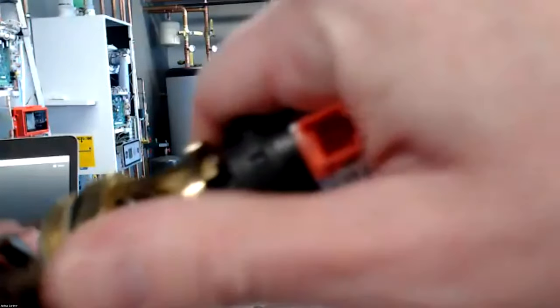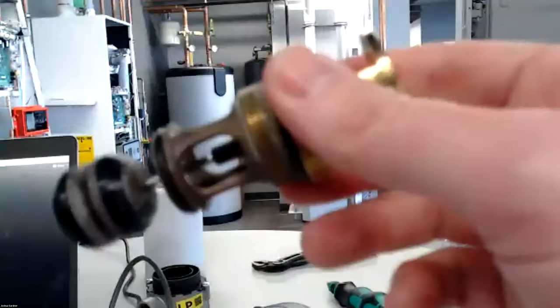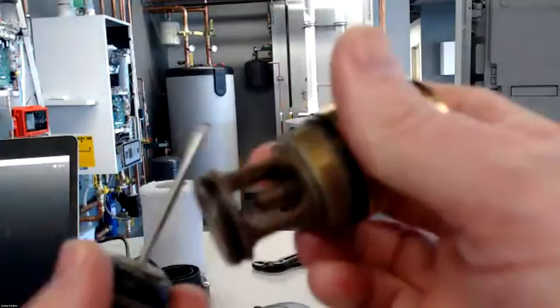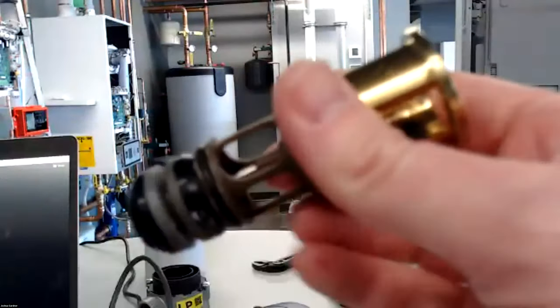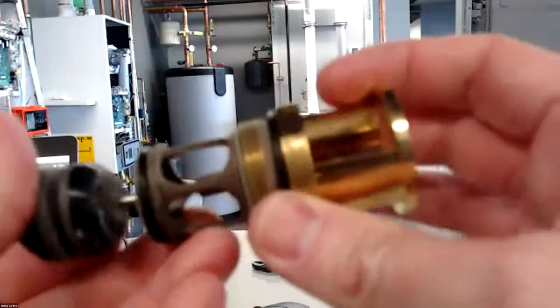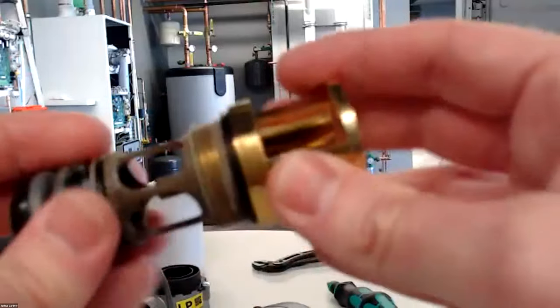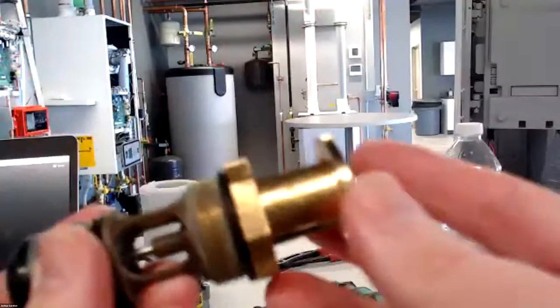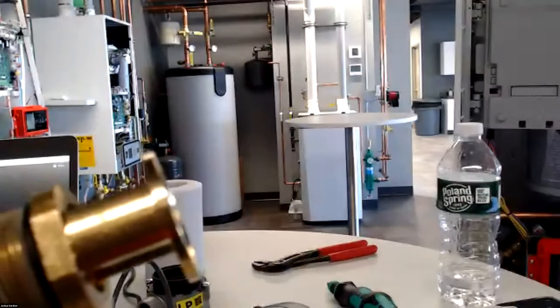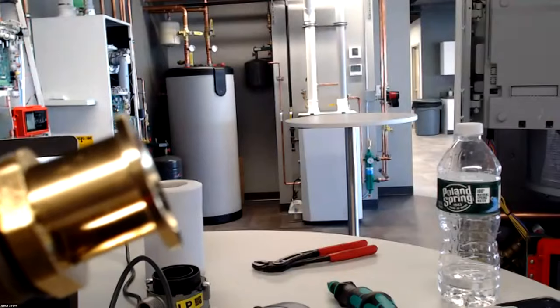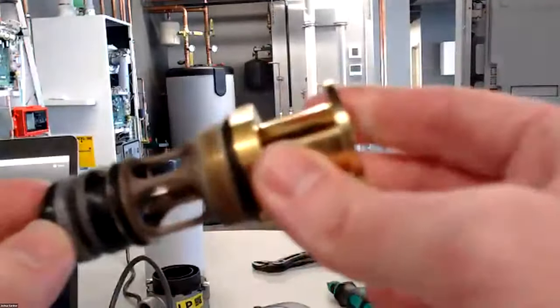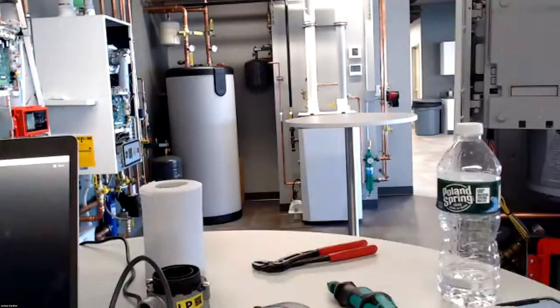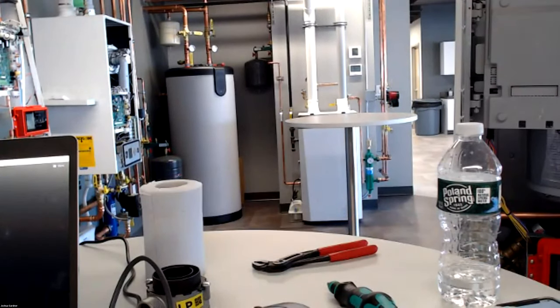So if you get that call and this thing is broken away from it, you're going to want to go ahead and open this and see if you got any debris lodged up in here preventing this thing from moving freely. That's one thing to note on the service side. It hasn't happened too much, but it has happened a couple times on a couple calls that I've seen. But that's how you service it, remedy it. What other things on the three-way valve?